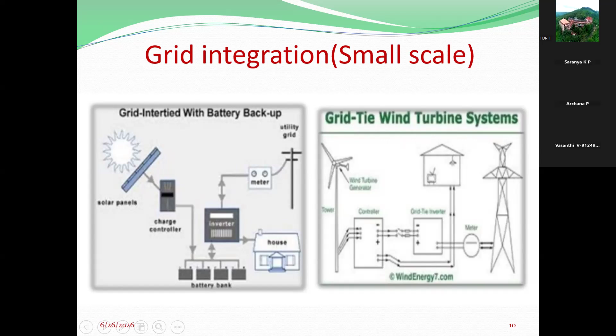So these are the renewable energy sources. The DC source will be generating power at a variable low DC voltage, such as fuel cell and photovoltaic energy sources. Then the AC source with a rectifier coupled to the DC link will be generating power at various AC voltages, with variable speed wind turbines. And there is a DC link capacitor which decouples the RES from the grid and also allows the independent control of converters on either side of the DC link.